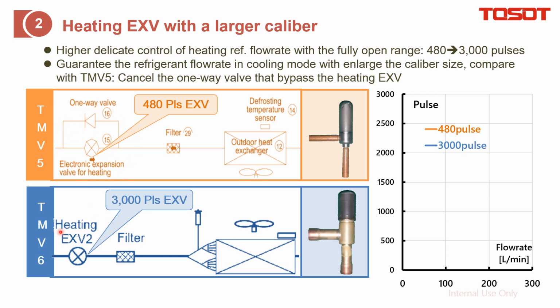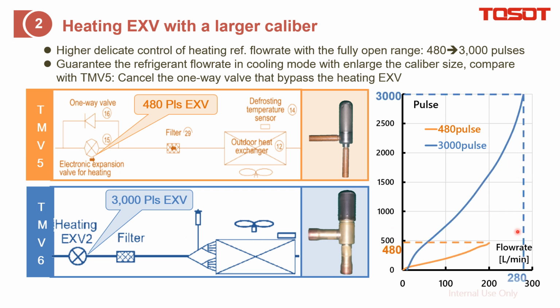But for the TMV6, we apply the bigger size EXV and with the fully open. So I just compare on this graph, you can find that it is 40% higher in the flow rate. And also that is the reason why we can cancel this check valve to guarantee more refrigerant can flow through this EXV as soon as possible in cooling.